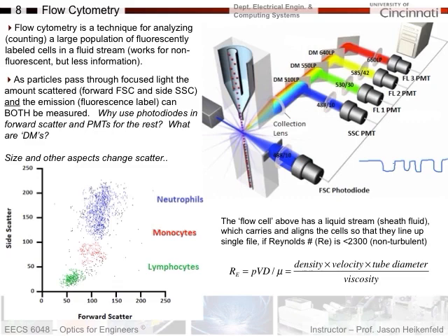So this way, what happens is the blue light causes the cell to fluoresce. And remember, you can stain regular cells maybe green and cancer cells yellow or red, okay? A regular cell comes in, fluoresces green, green light goes to this PMT, and it says, I just counted a regular cell. And PMTs can be really fast too. They can detect very quickly as well. And regular cells are coming through, then a cancer cell comes through, and let's say it's stained red. Red fluorescence comes in, and it counts that it just found one cancer cell, for example. Okay? And so you need these photomultiplier tubes because they have such low light sensitivity that they can do the counting you need.